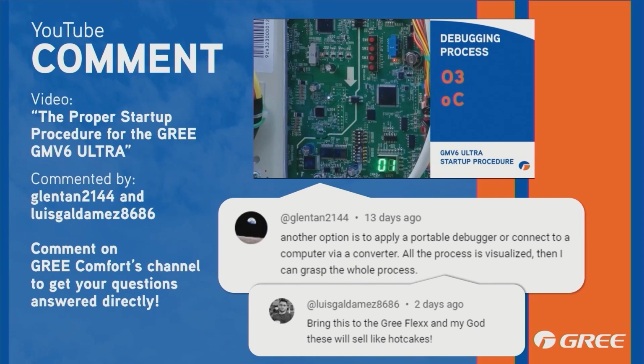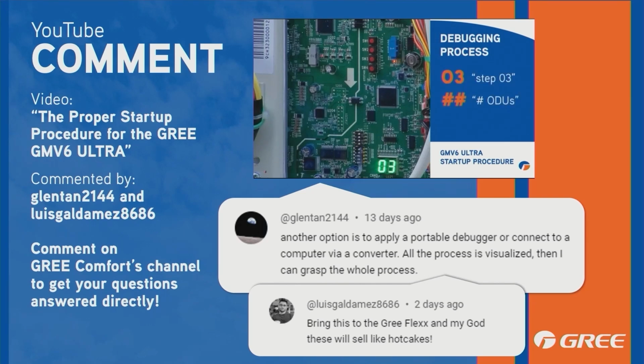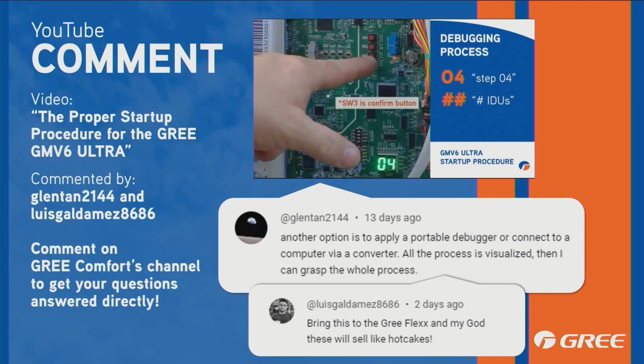But as far as startup goes, when I started up the one that I was testing, I had the portable service tool right there, and I just used the board because it was so easy just to toggle. It's just pushing a couple buttons and letting it go through its process. So whether you're doing it with the service tool or just by pushing the buttons right there on the board, it's a pretty simple process to run through. Now, if you have a glitch in it, in other words, you have an error code, this service tool might give you a little bit more information. Generally speaking, if your debugging process stops and you get an error code, then you can refer to the service manual.